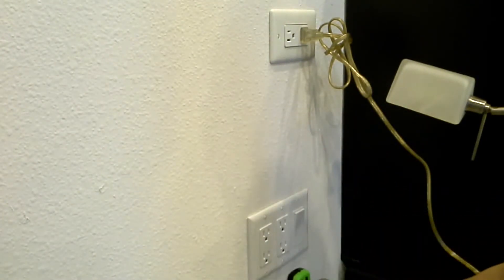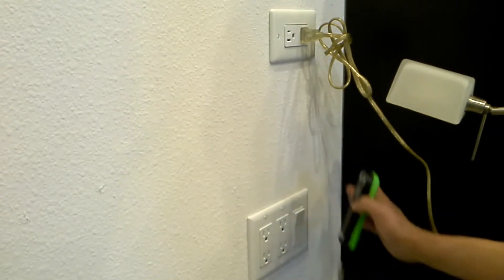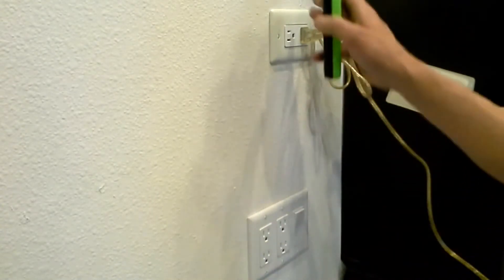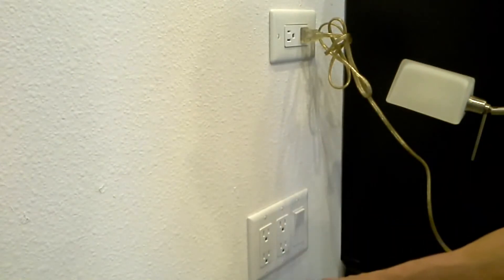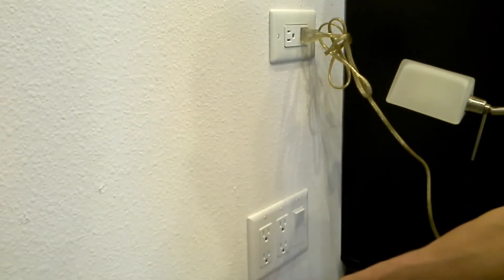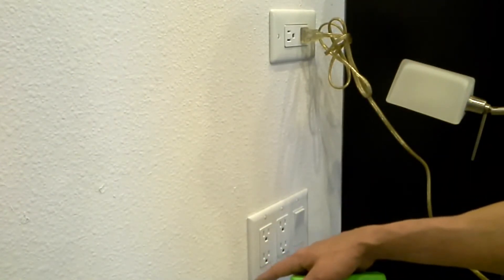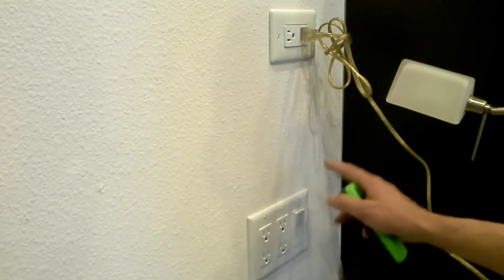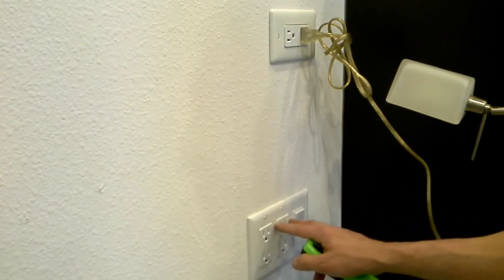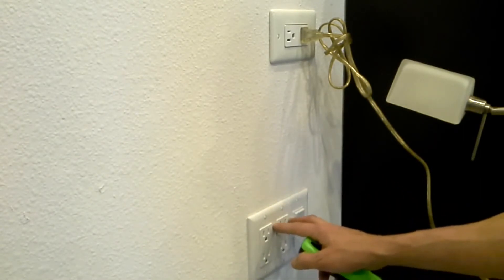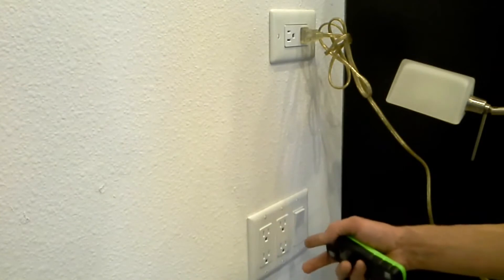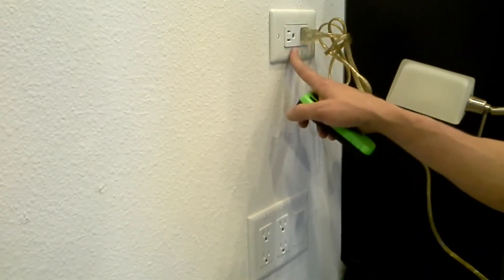There's a stud over here on this side and a stud over here. I cut these out. I ran the wire from the other box on the other side of the wall up through the hole. We put a remodel three gang outlet box in here and then we ran another wire from here up to this one and cut the hole there, put another one gang outlet box in here.